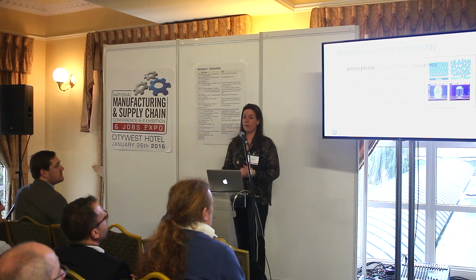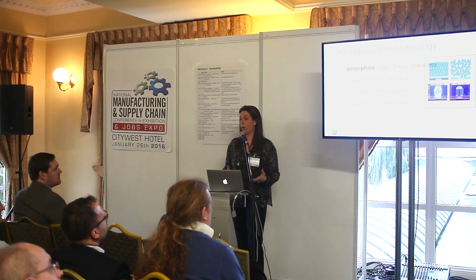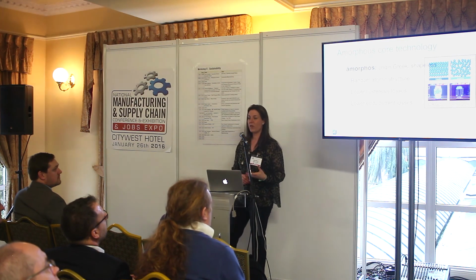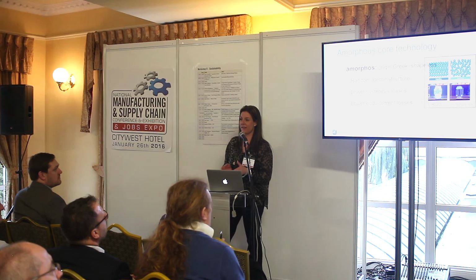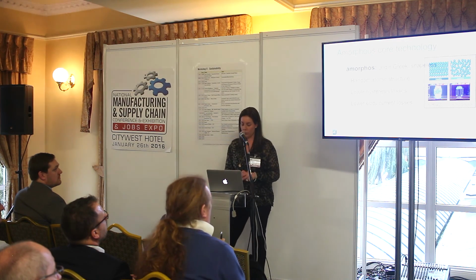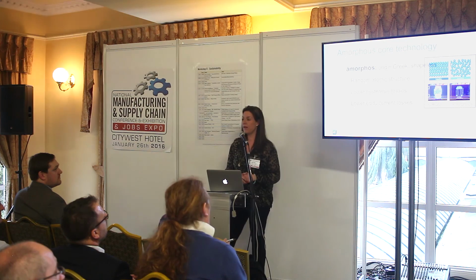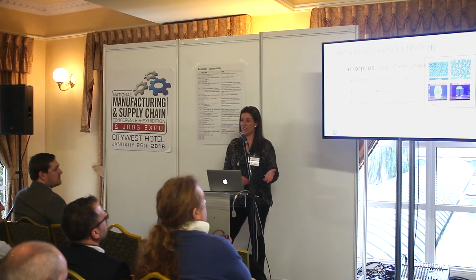I apologise for that. So, amorphous - the word comes from Greek and means shapeless. You can see in the imagery on the right that molecular appearance is very random. During the magnetisation process, because of the random structure, less friction is created. I like to look at things simply: less friction means lower heat and fewer losses. That's how we achieve that with the amorphous core. In the infrared imagery on the right, you can see the amorphous core material is far cooler than the standard core steel other manufacturers use, shown on the left.